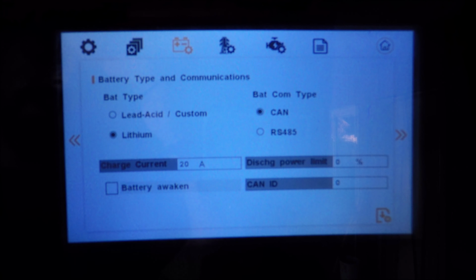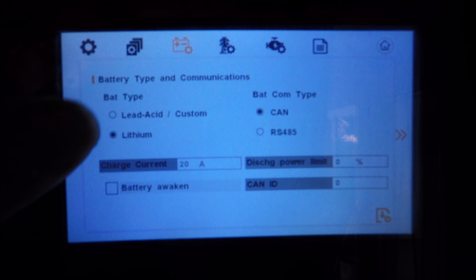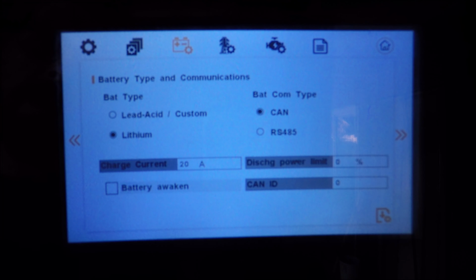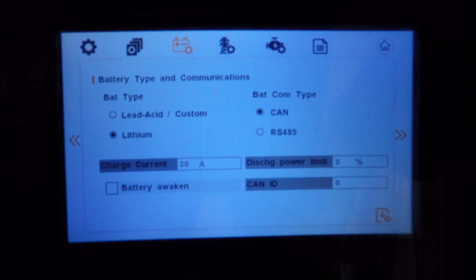There are two primary battery types that you can choose from: lead acid custom, and really this should just be labeled custom, and lithium. If you choose lithium and your battery has CAN communication, you can simply plug a standard Cat5 cable between the battery and the inverter into the battery COM port on the inverter, and by default most batteries will go ahead and communicate and work. If not, you can try setting your battery on your battery screen to a different communication type. So currently lithium is selected. We have CAN as the battery communication type.